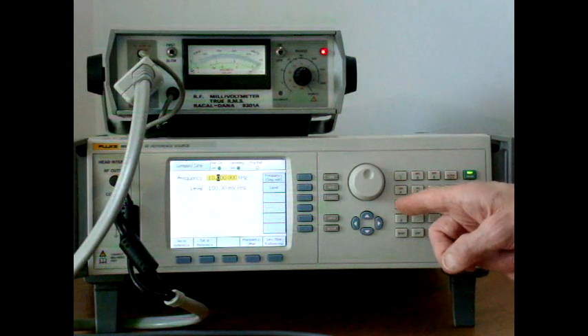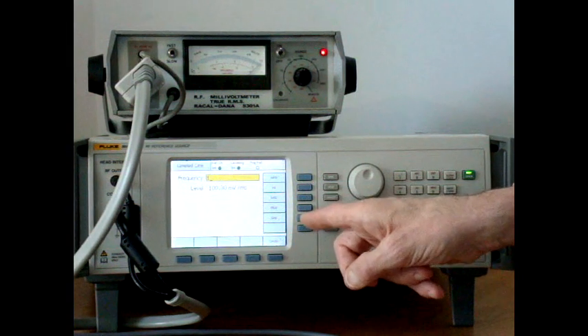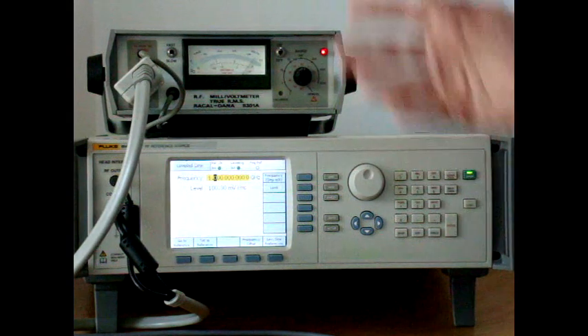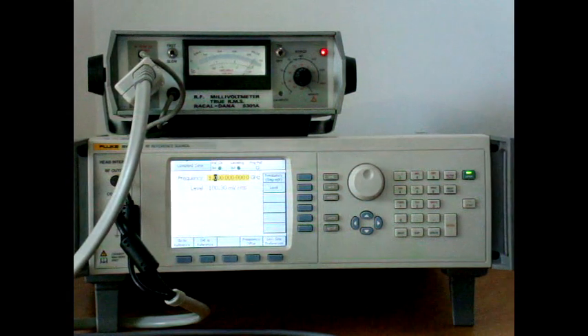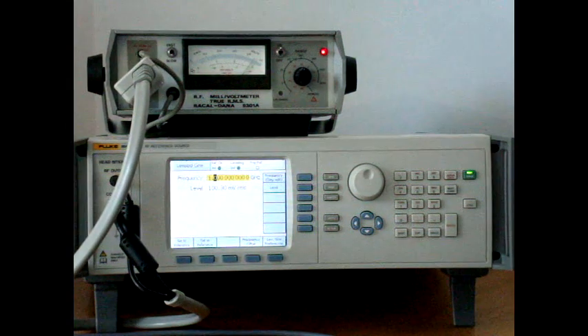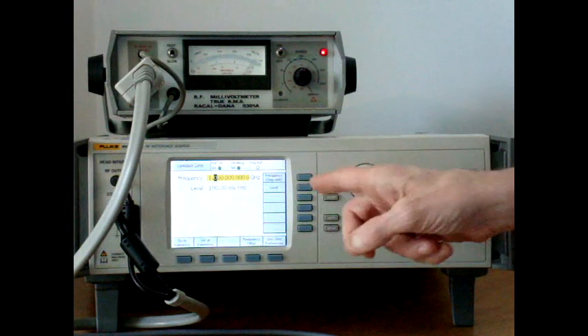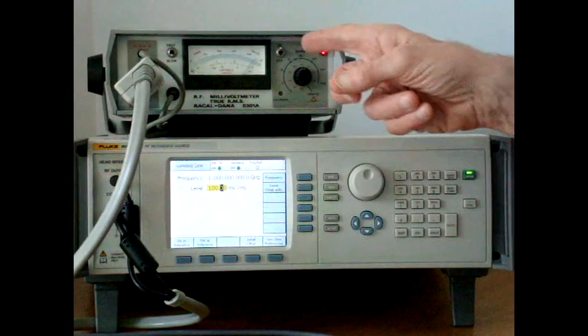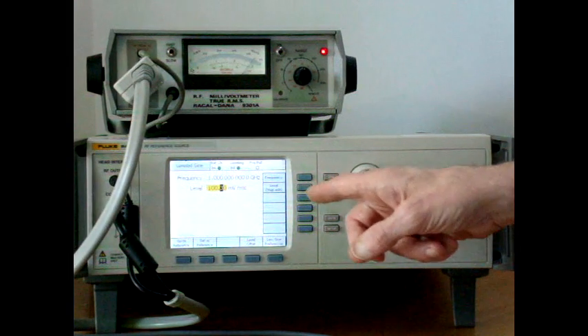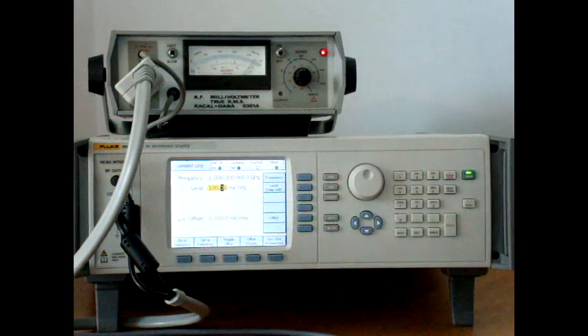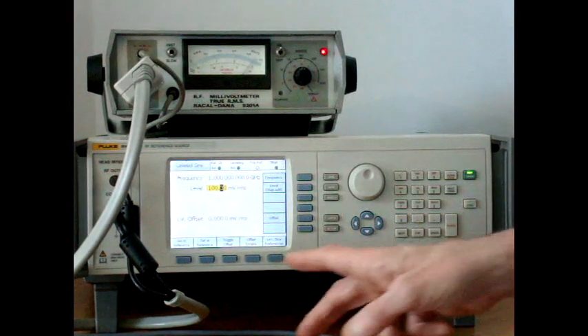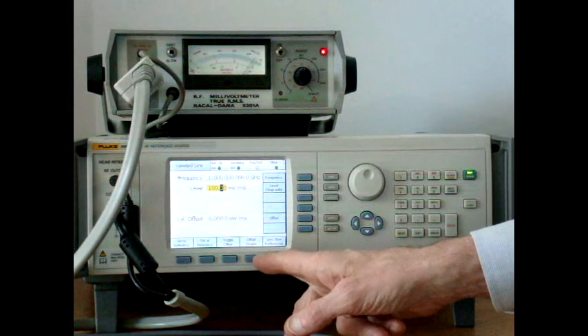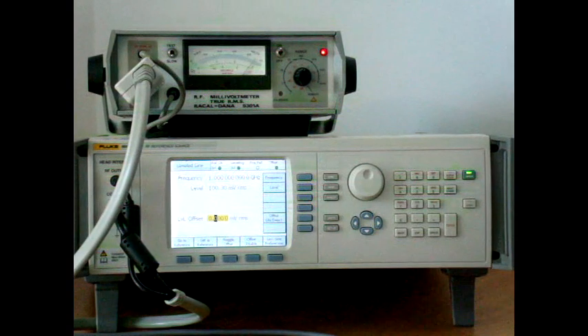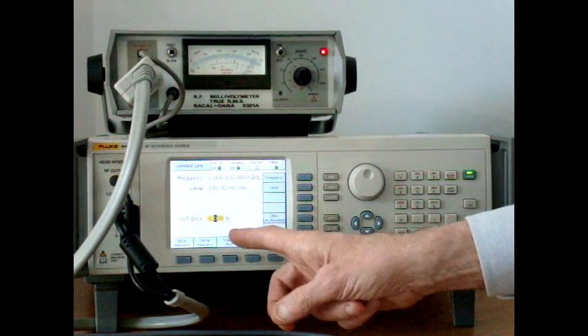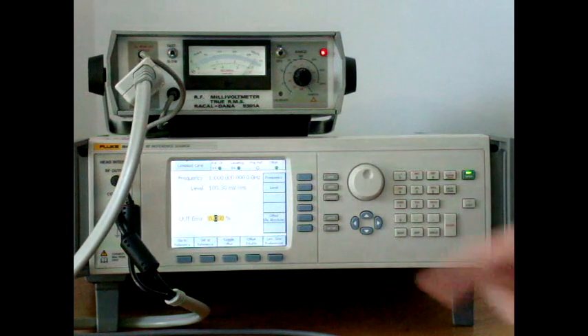1 GHz. Wait for the reading to settle, and you notice we have an error. And we can make use of a feature of the 9640 to show us that error directly in terms of percentage of the UUT. If I press the error key, offset key, I can show that offset in terms of the UUT error. So I can get a direct reading of the UUT error in percent.